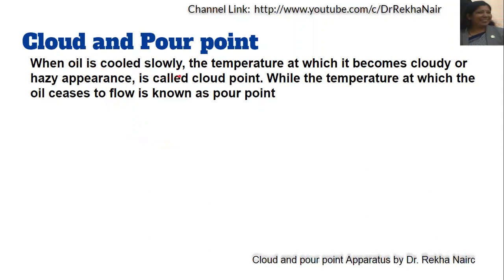When oil is cooled slowly, that is, when the temperature of the oil is decreased slowly, there comes a temperature where it gives a cloudy or hazy appearance. The temperature at which it gives a cloudy or hazy appearance is called the cloud point.